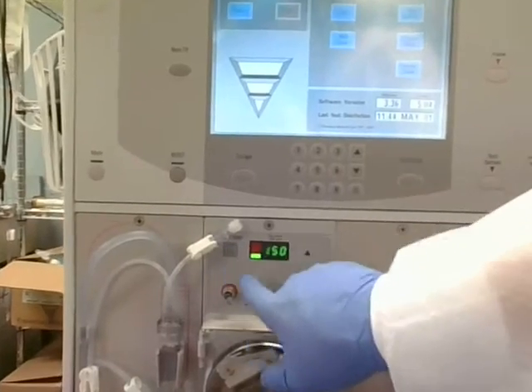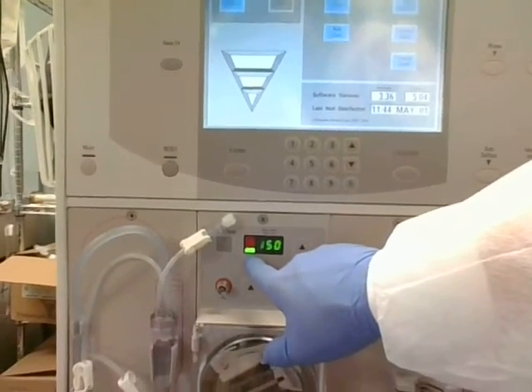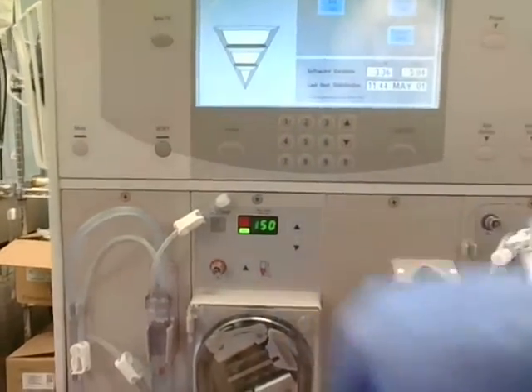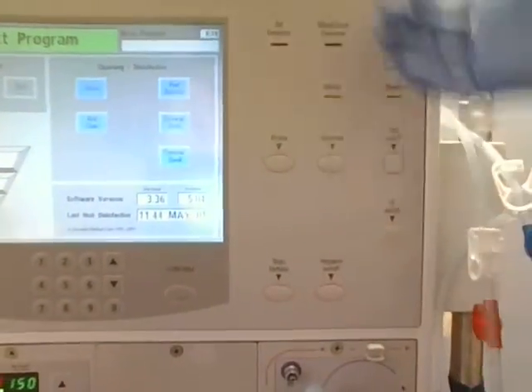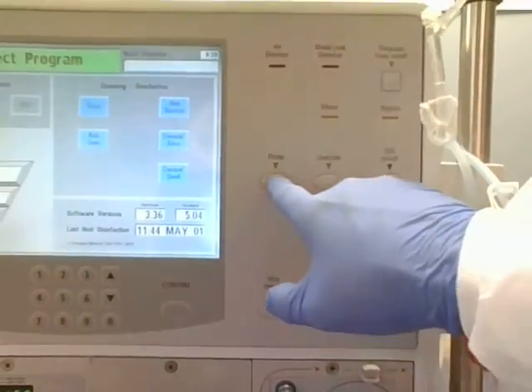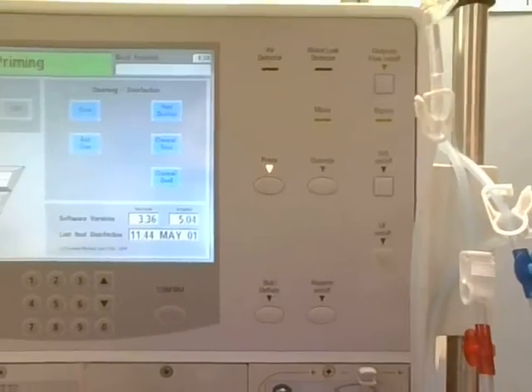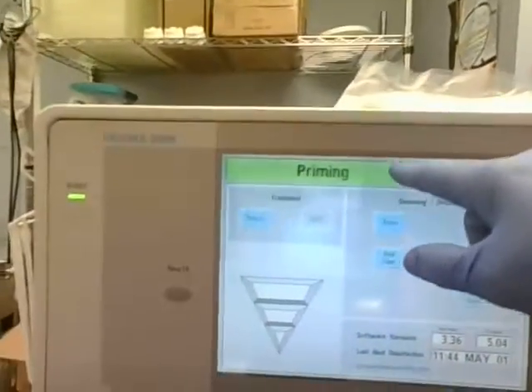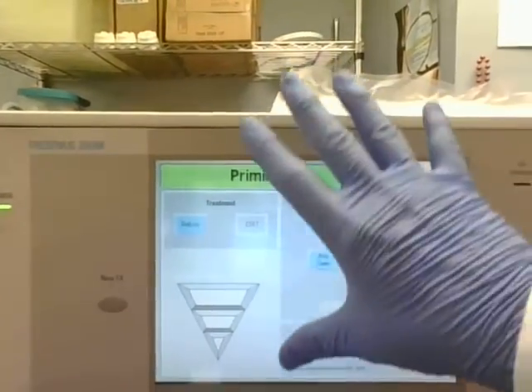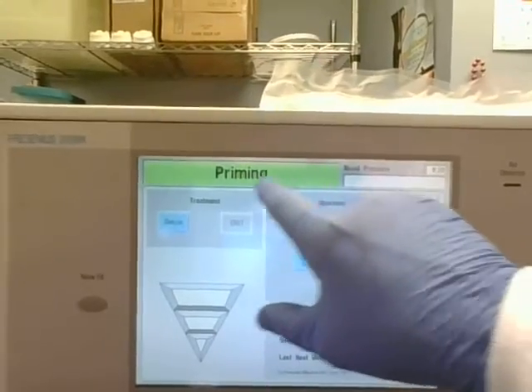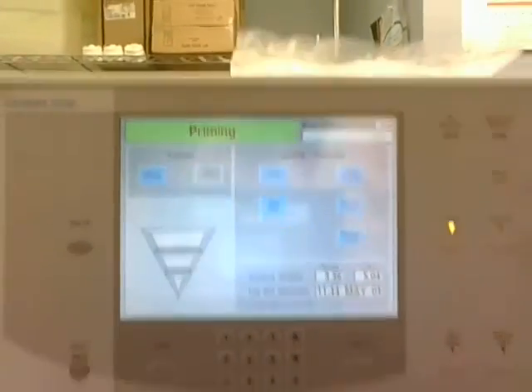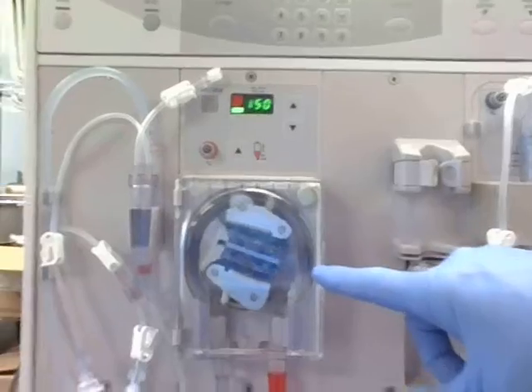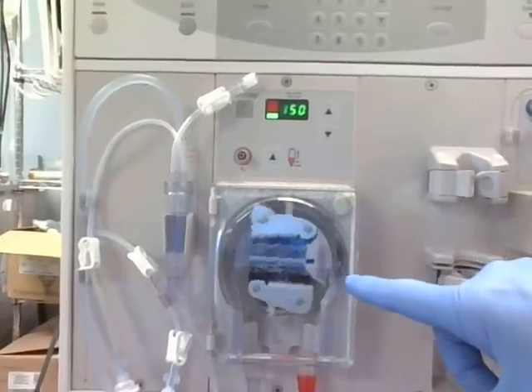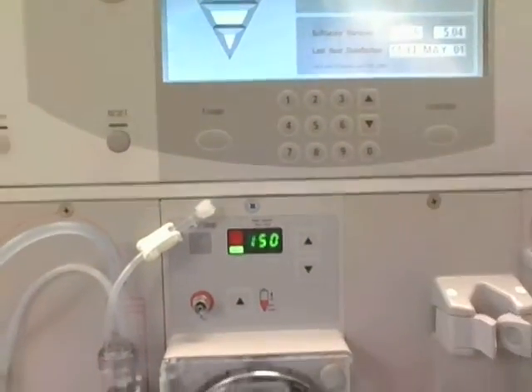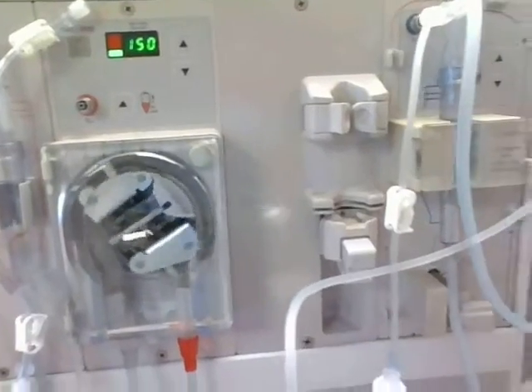I'm going to turn that on. You know it's on when the green light comes on and your numbers stop blinking. Then over here on my control panel, I'm going to push the button that says prime. Notice my marquee here on the face of my machine, on my touch screen. It says that it is priming and my blood pump is moving. All right, it is moving at 150 milliliters per minute.